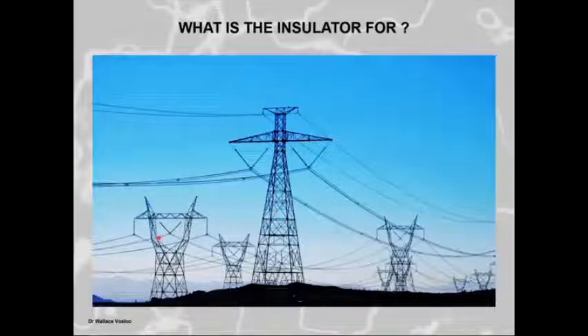These insulators, obviously, are used in different configurations, like I and V configurations. And yeah, we've got a double V here. And then they also tension. So this is suspending, the suspension insulator. Then you've got the insulator where you have one on this side, one on that side, with a jumper in between, and that is then taking strain from the conductor. This is suspending the conductor.